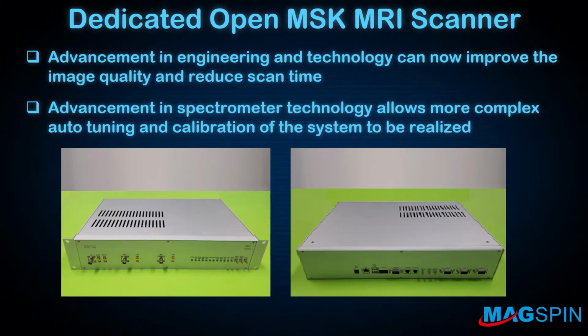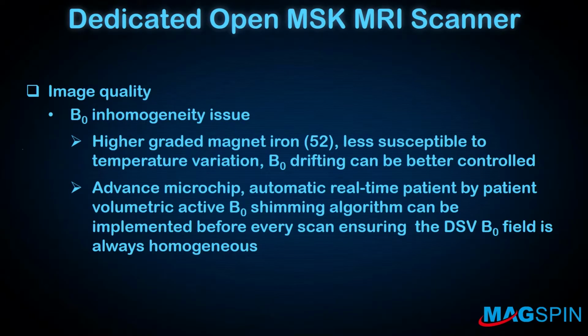So we can do more complex auto tuning and calibration of the system so that it can be the most optimum system, with small optimums when they are doing the imaging scanning. So from the low field MRI scanners, the image qualities mainly can be classified into three different problems.